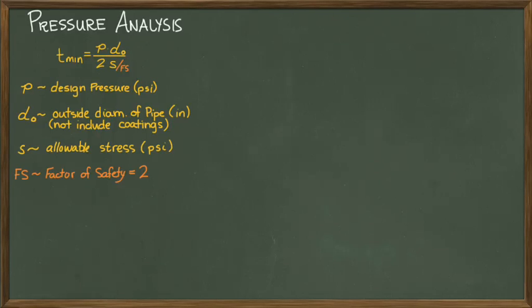Please note that the allowable stress is a function of the specific type of steel used as determined by the appropriate ASTM standard. Those listed in M11 include ASTM A36 steel as well as A283, A570, and A572. When I was getting paid for doing these calculations we typically specified ASTM A570 grade 30, meaning 30 KSI as the maximum allowable stress.